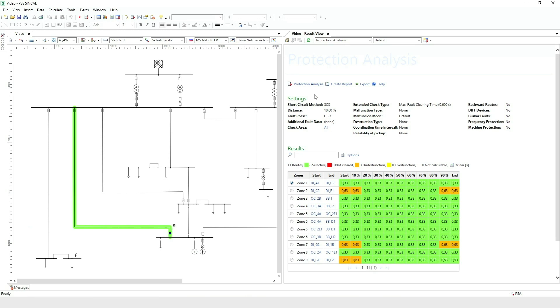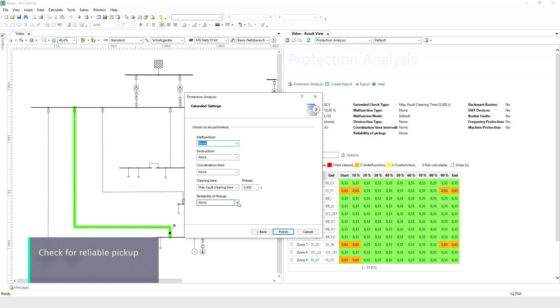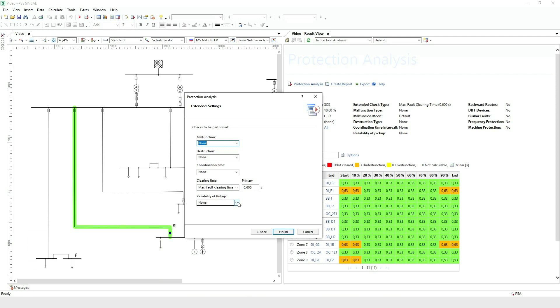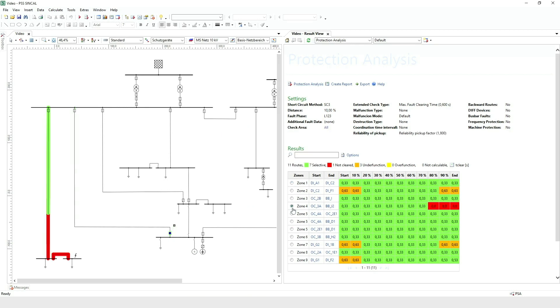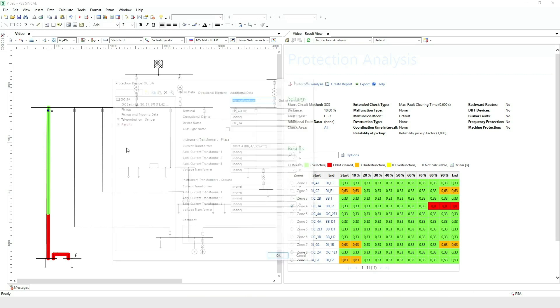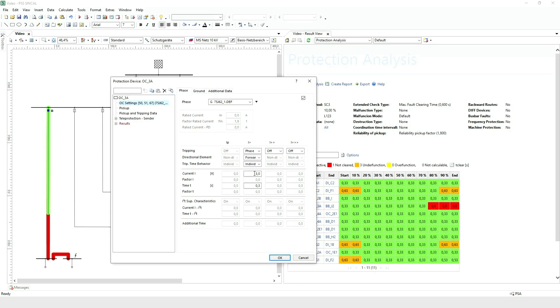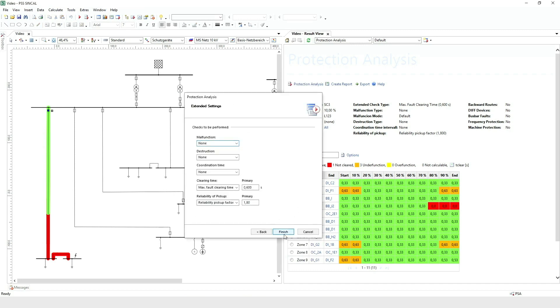The second essential check is for reliable pickup — here we see if the protection device is able to pick up at the minimum short circuit current under the consideration of a reliability factor. To do this, activate the reliability pickup factor in the extended settings and set it. With these settings, we see some fault locations where pickup of the protection can't be guaranteed. You can try to make the setting more sensitive, but need to consider the load current. We can change the pickup and perform the protection analysis again.